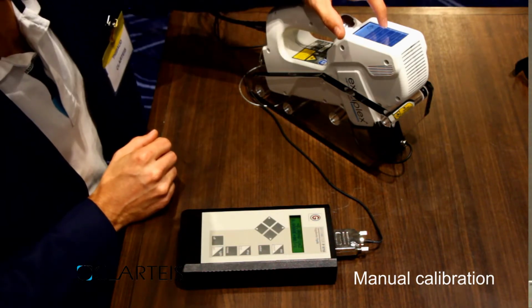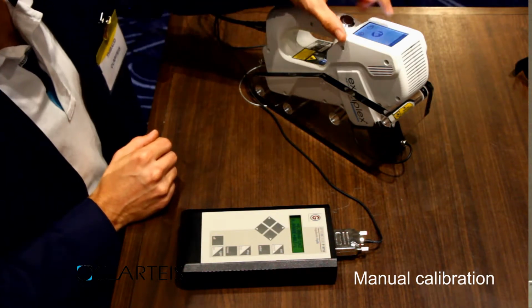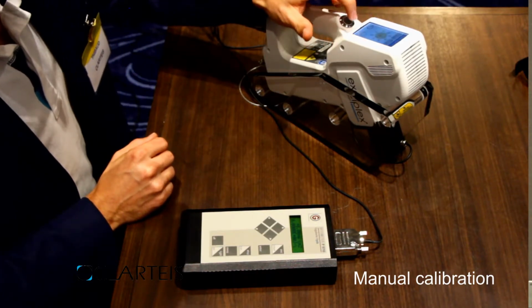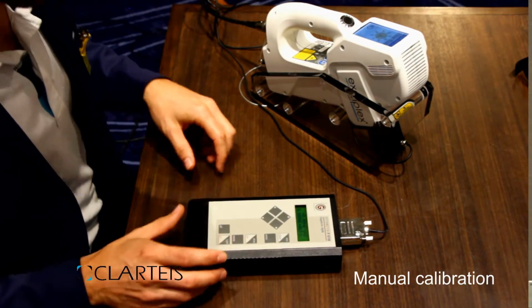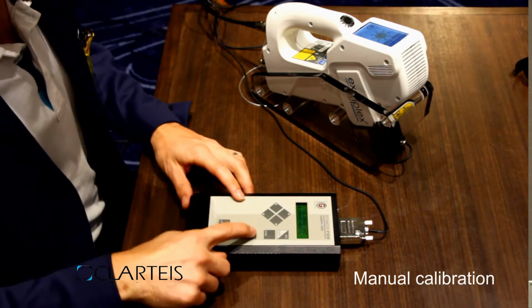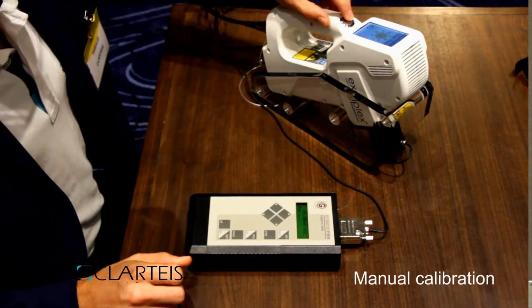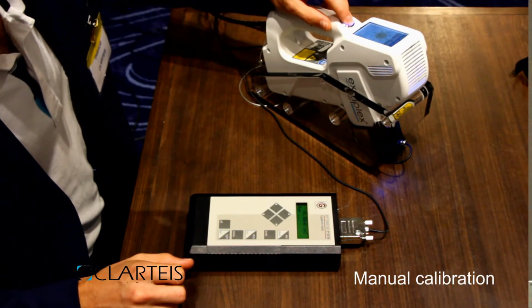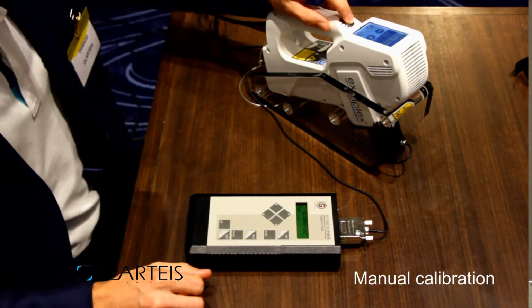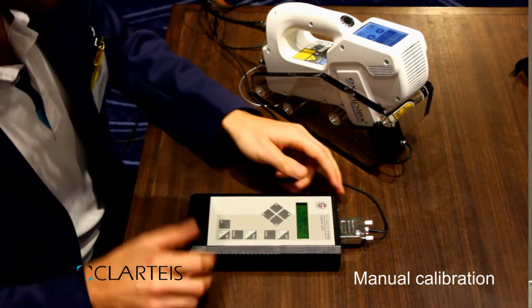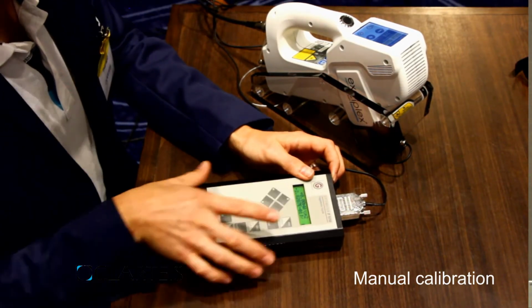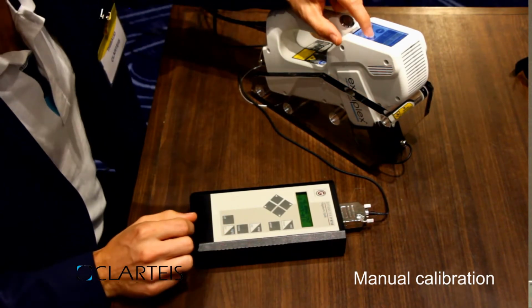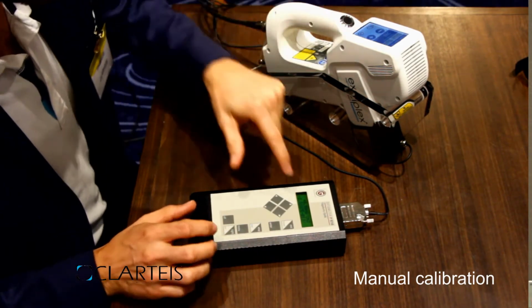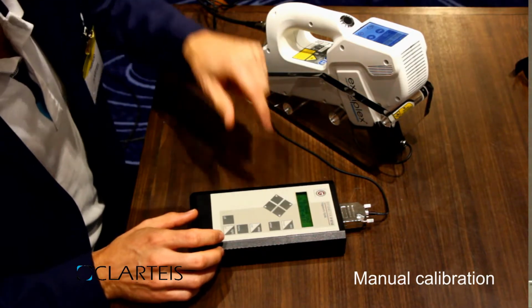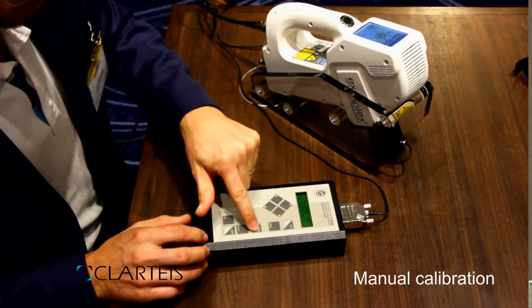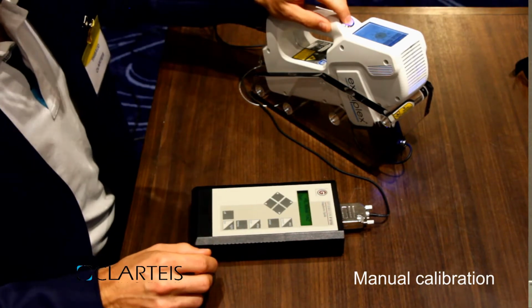Now you can go to the calibrate menu and perform a calibration. So, in order to perform a calibration, you need to press run and start. This will make a dose measurement. You stop, you get the value from the optometer and you refer the value to the Exciplex. You will have to round the value. Press OK and start again. You will have to perform this 5 times.